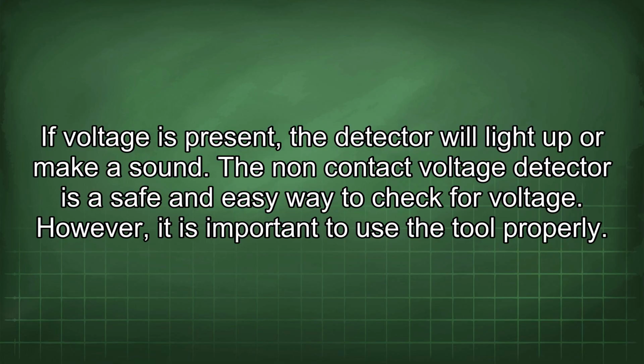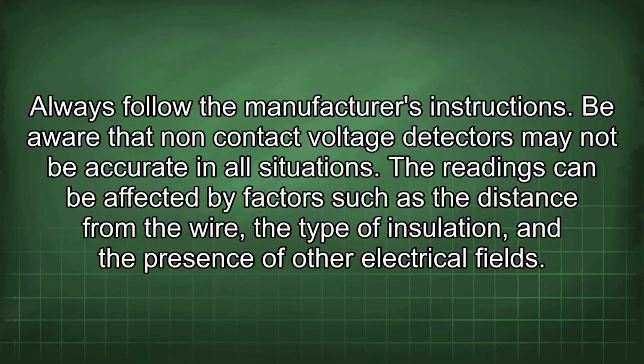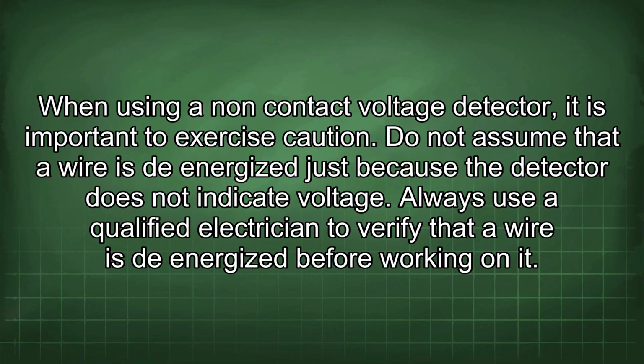However, it is important to use the tool properly. Always follow the manufacturer's instructions. Be aware that non-contact voltage detectors may not be accurate in all situations. The readings can be affected by factors such as the distance from the wire, the type of insulation, and the presence of other electrical fields. When using a non-contact voltage detector, it is important to exercise caution. Do not assume that a wire is de-energized just because the detector does not indicate voltage. Always use a qualified electrician to verify that a wire is de-energized before working on it.